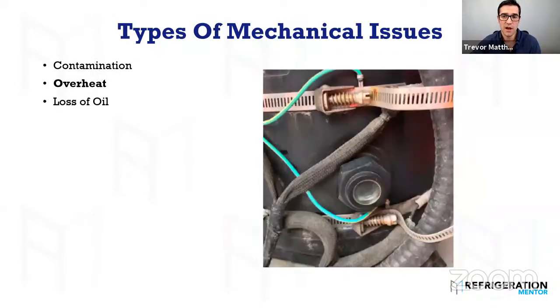The next one, loss of oil. This one's really hard to tell, especially if you don't have a sight glass. For example, this one has a sight glass. There's no oil in it. Where's the oil? So you need to understand if it's sloping back to the compressor properly. Are your lines sized properly? Do you have a trap? There's so many things you need to understand.